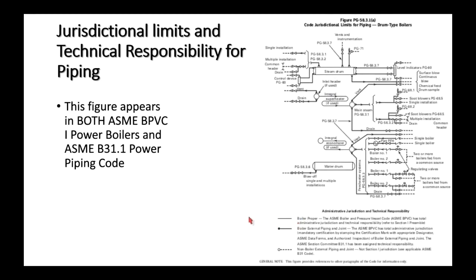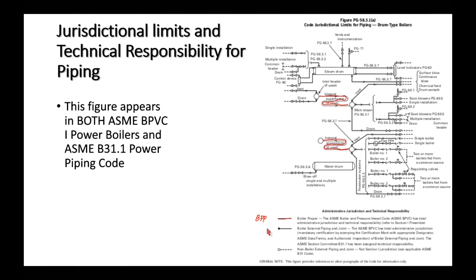Let's talk about boiler proper piping, boiler external piping, and non-boiler external piping. Boiler proper piping actually forms part of the boiler itself — examples are integral economizers and superheaters. This is a very small fraction of boiler piping. Boiler external piping connects the boiler to something external and goes up to the first required valve — for example, the first isolation valve on a gauge glass, continuous blow-off, or vent line.